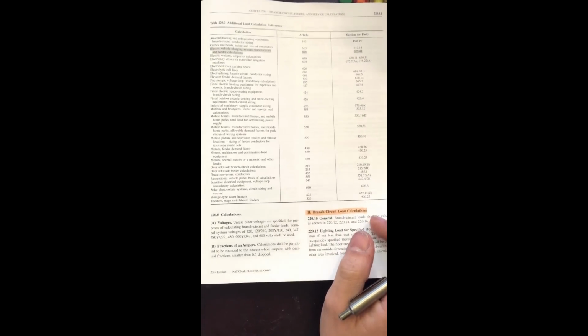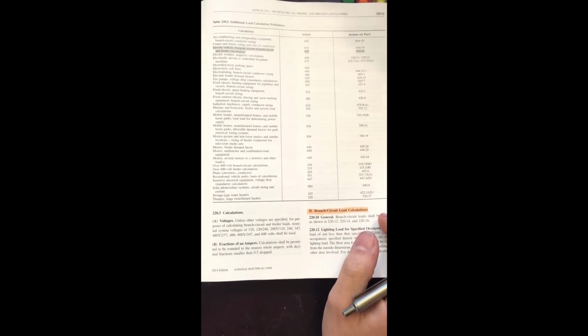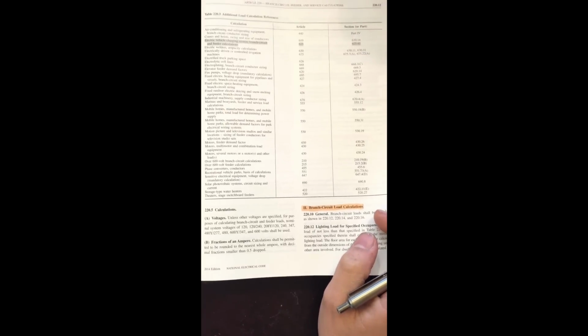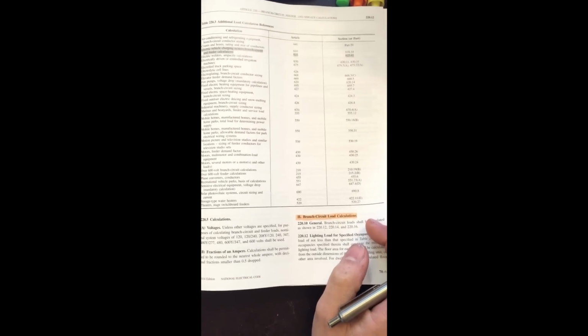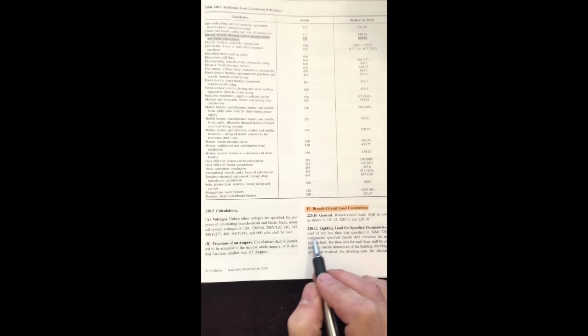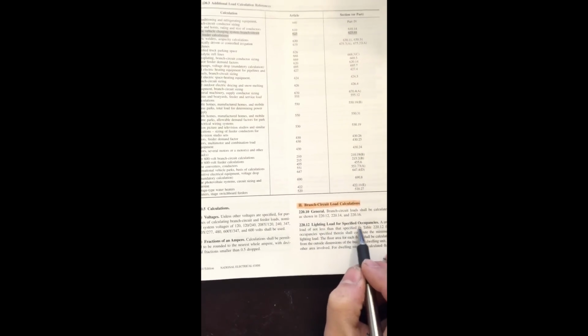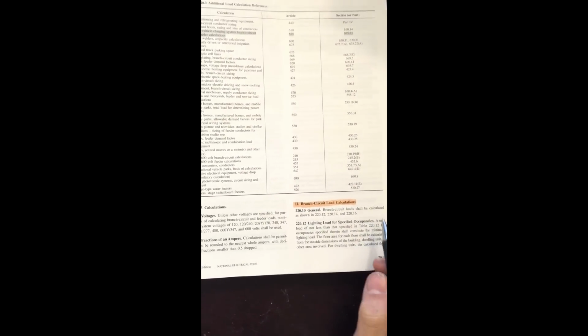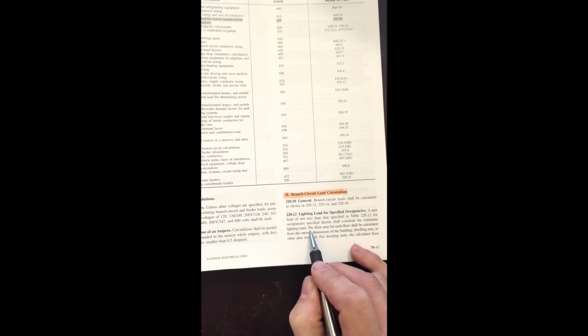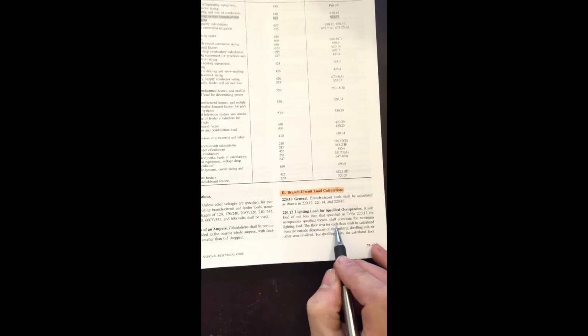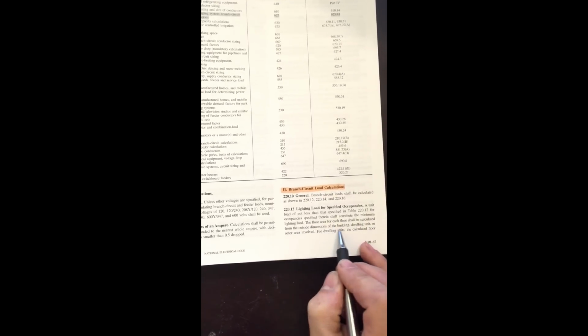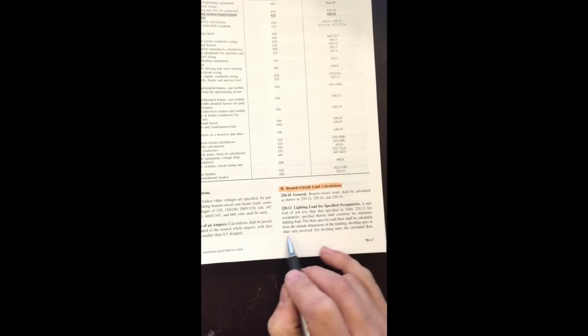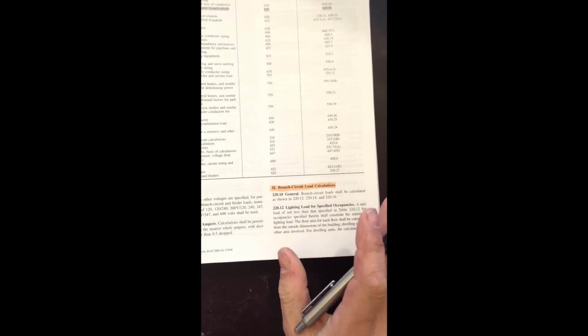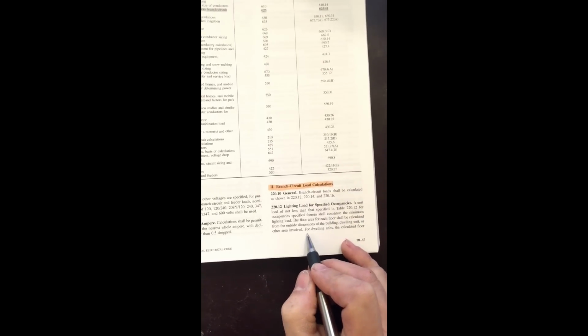Residential services fall under basically one of two categories. They fall under what we call the standard method of calculation, which you'll notice on page 67 under 220.12, lighting load for specified occupancies. The last part down here, the second sentence, starts with the floor area for each floor should be calculated from the outside dimensions of the building, dwelling unit, or other area involved. All right, so this applies to both commercial and residential. However, the next sentence is residential only.